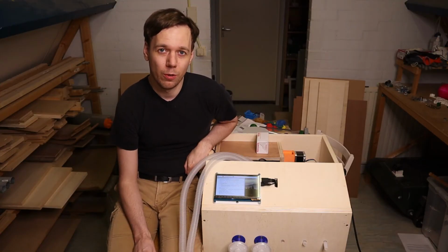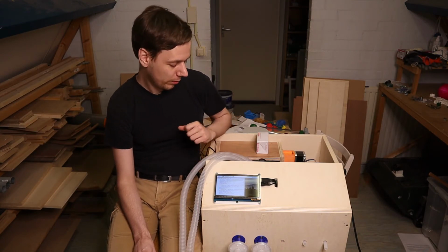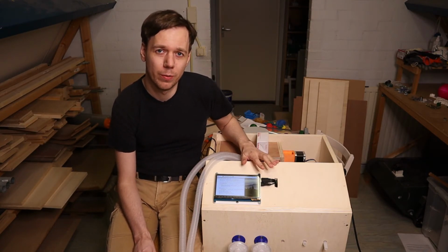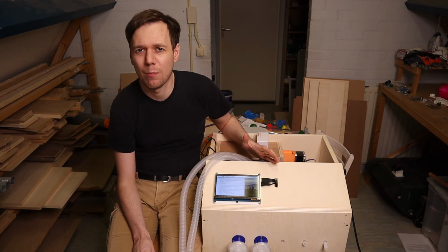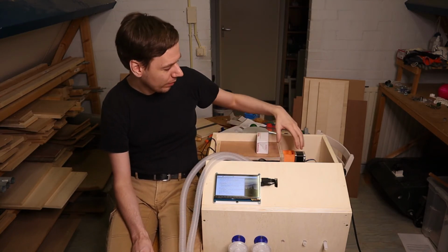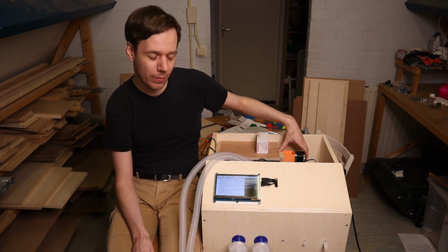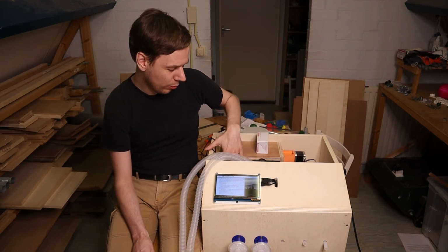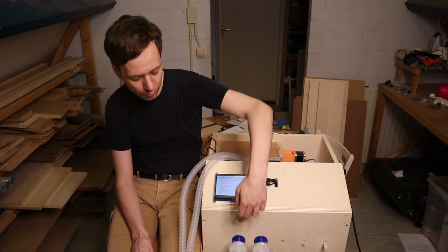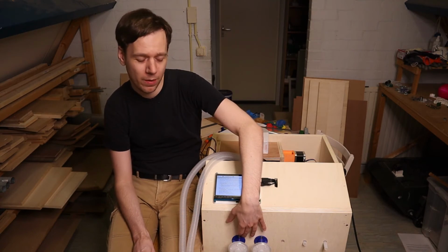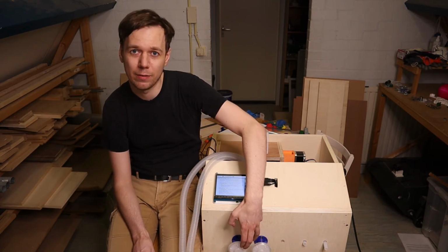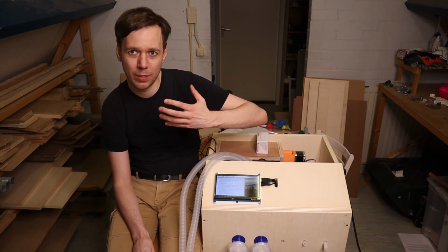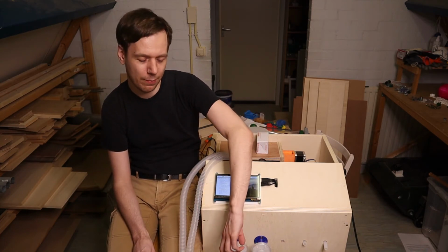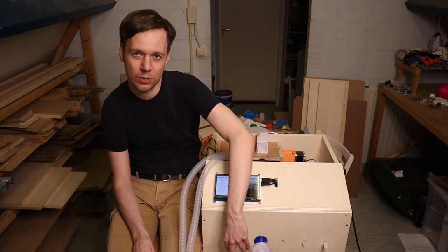The final points on the software is first the alarms. Currently none of the alarms are implemented, and one of the example alarms is if you were to activate the pump and you do not measure the pressure increasing, but you do measure a flow. That means that there is air leaving the system, but it's not going into the patient, it's just going straight out. That means that there is a leak or a disconnect in the hose.